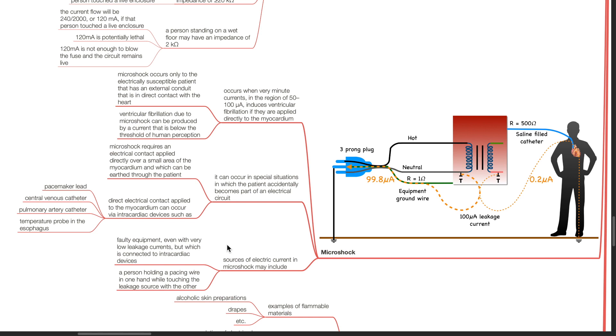Direct electrical contact applied to the myocardium can occur via intracardiac devices such as pacemaker lead, central venous catheter, pulmonary artery catheter, and temperature probe in the esophagus. Sources of electric current in microshock may include faulty equipment even with very low leakage currents but which is connected to intracardiac devices, or a person holding a pacing wire in one hand while touching the leakage source with the other.